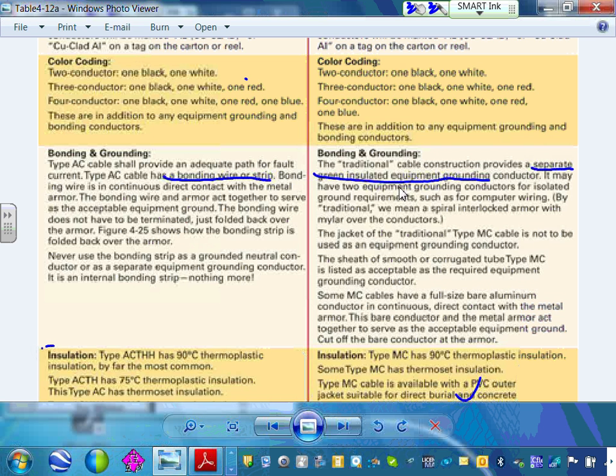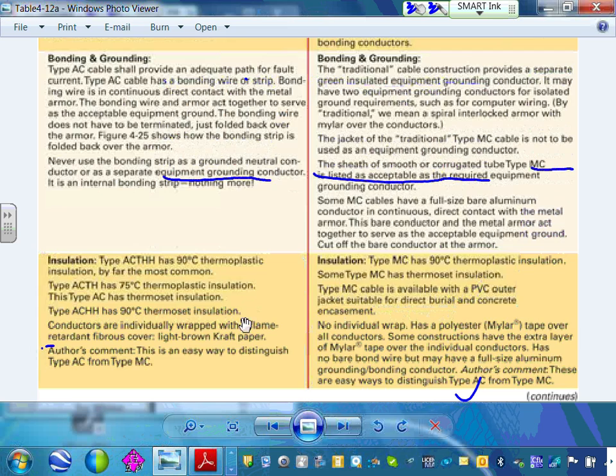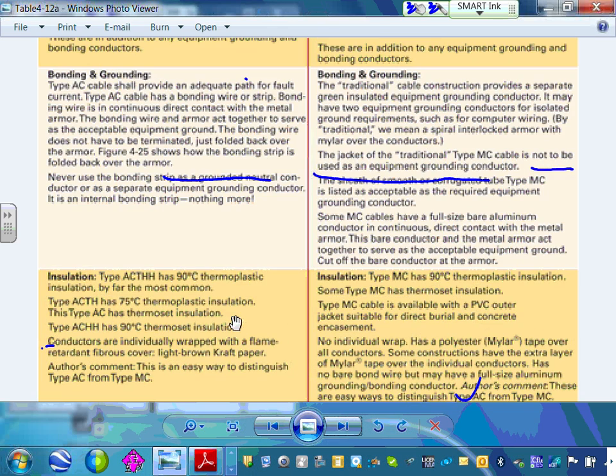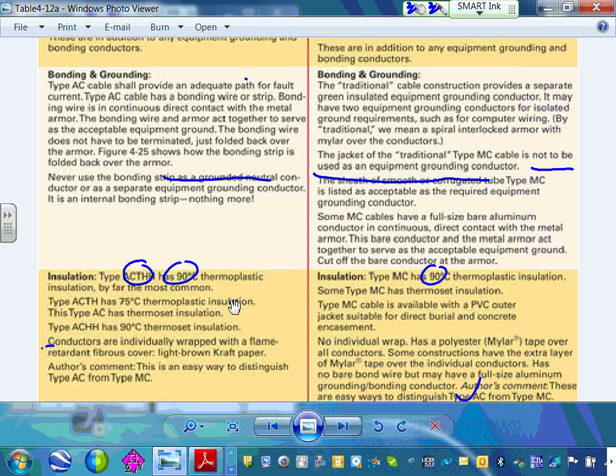Now here's another superiority, guys. In terms of insulation, this comes with THHN 90-degree, and this is also 90-degree MC cable. In terms of 75, also THWN 75. The ampacity of these conductors, guys, typically is based on the 75-degree column. Both of them are based on the 75-degree column, depending on the lugs.